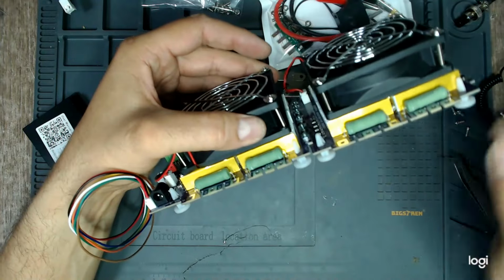So I have connected my electronic load and it is set up to 300 watts, in constant power mode, and I will start at 100 watts and go from there. I have my oscilloscope ground lead connected to my earth connection here, and the probe tip connected to the output ground of the power supply module, because as I said, I want to test the leakage between the output ground and earth.